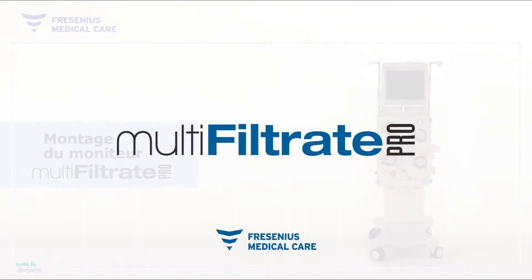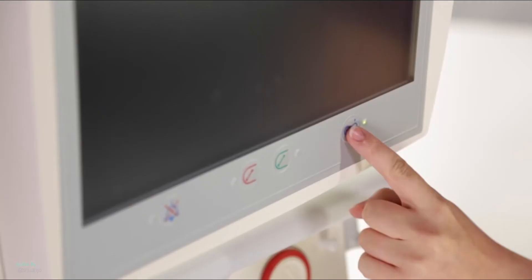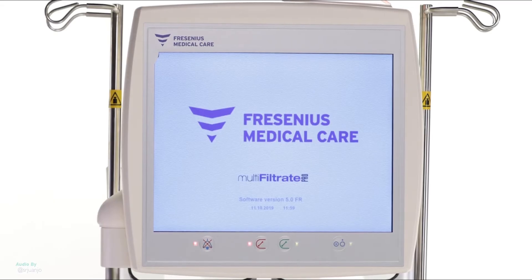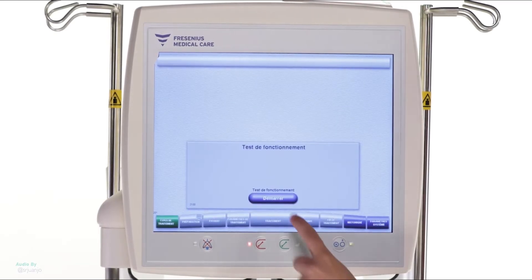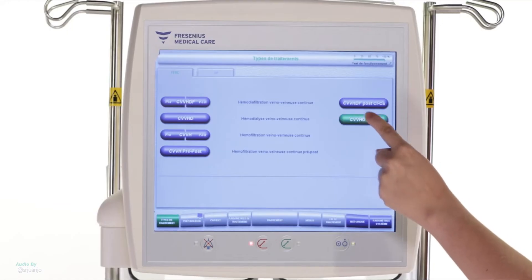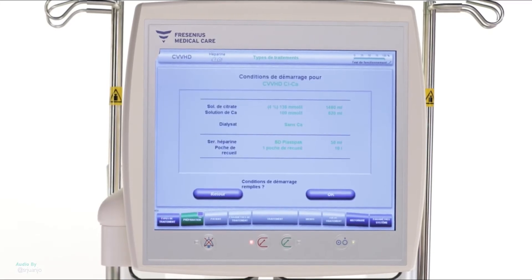Mounting the Multi-Filtrate Pro. To turn on the device, press the button for a few seconds. Then press Start to launch the operation test. While doing the test, select the CVVHD Ci-Ca Treatment Mode. Check what is needed before starting, and then press OK.